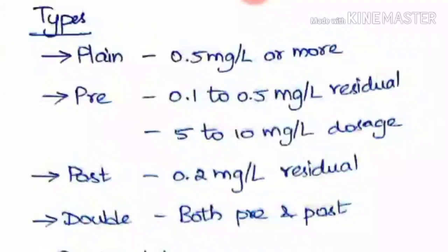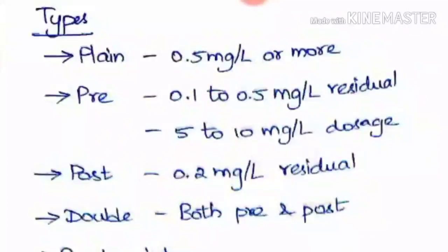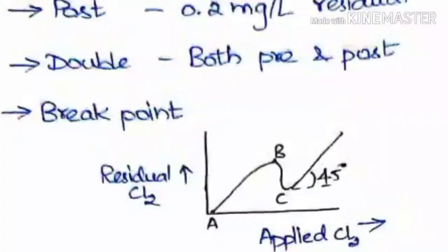In pre-chlorination, the residual chlorine must be 0.1 to 0.5 mg/L. Post chlorination is simply the residual that has to be maintained in the water at 0.2 mg/L. Double chlorination means applying both pre-chlorination and post-chlorination when the turbidity of water is high and the water is highly contaminated.